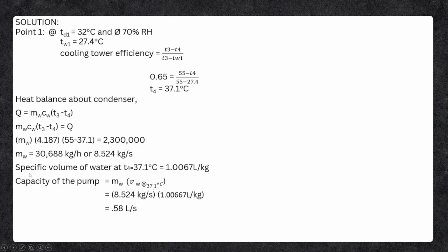So we get the specific volume of water at temperature 4, which is 37.1 degrees Celsius, using the psychrometric chart. Plotting that, we get 1.0067 liter per kilogram as the specific volume of water. So the formula to get the capacity of the pump is mass times volume of water. Our mass of water is 8.524 kg per second times 1.0067 liter per kilogram. We get the pump capacity as 0.58 liter per second.